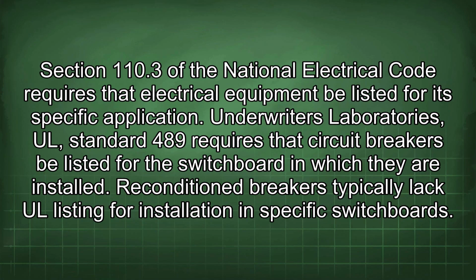Section 110.3 of the National Electrical Code requires that electrical equipment be listed for its specific application. Underwriters Laboratories UL Standard 489 requires that circuit breakers be listed for the switchboard in which they are installed. Reconditioned breakers typically lack UL listing for installation in specific switchboards.